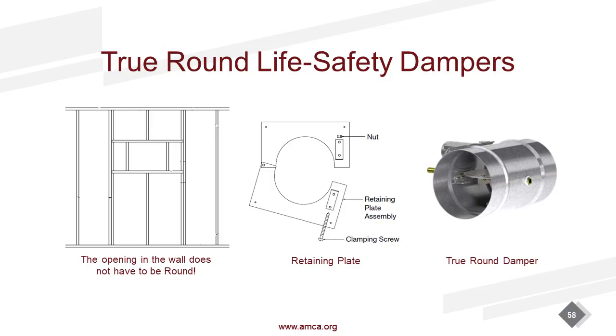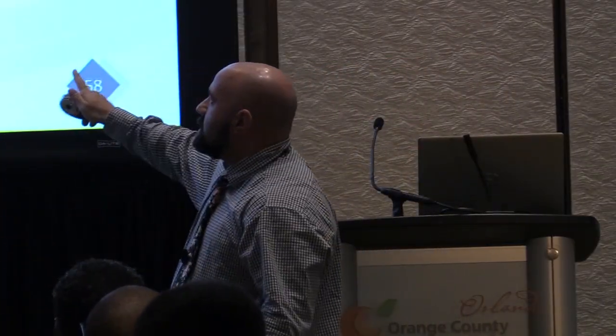But the first thing to say, from the perspective of the code, a true round damper is the same as a square damper. It's got the same rating, same testing. There's nothing different. For the installation, that is the framing of a damper that is square. That is also the framing of a damper that is round. They come with a retaining plate. Fire smoke dampers and fire dampers require retaining angles in their installation. That's a structural component that keeps the damper from falling out of the wall in the event of debris falling out of the ceiling. We don't put a retaining angle on round dampers. We put a retaining plate. That square plate goes over the square hole. I've got the required clearance around that opening with that plate.